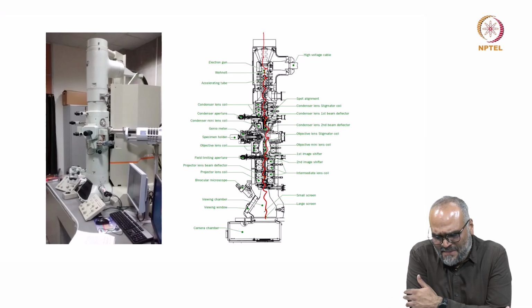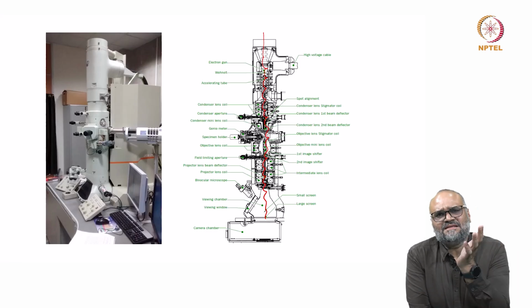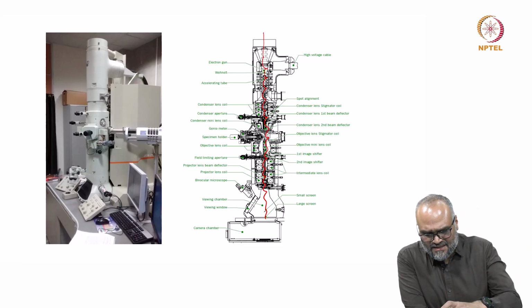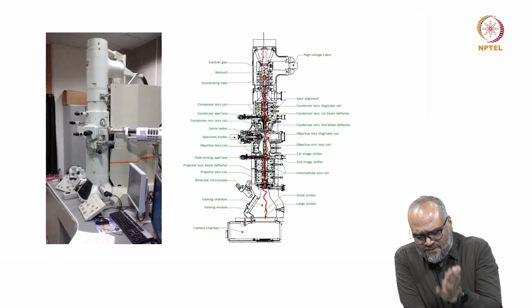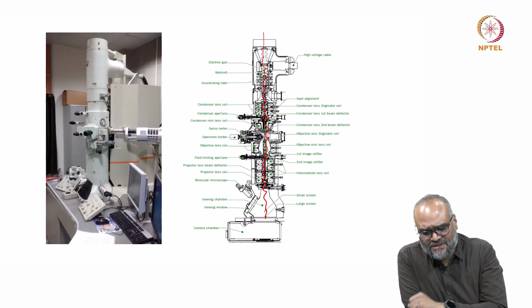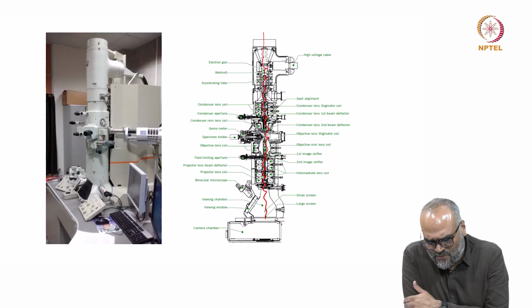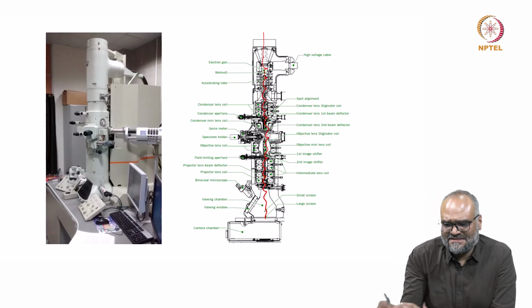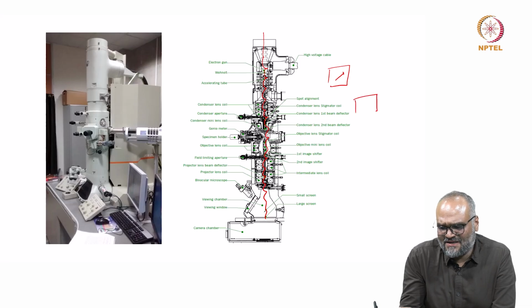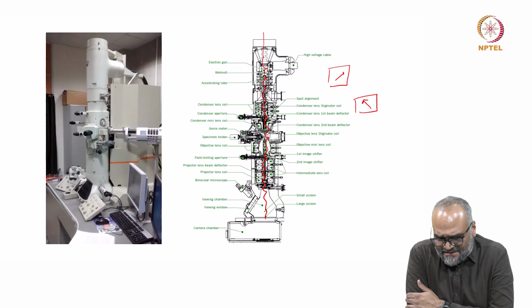Now, the modern day microscopes, when there is a change in the strength of the objective and the illumination lenses, when I switch from one mode to another mode, can compensate for this rotation. But in the old school microscopes, even in this 2100 microscope, you typically end up seeing an image rotation. So I might start with imaging in an orientation like this. When I increase the magnification, I might end up with an orientation of your feature in this particular direction.